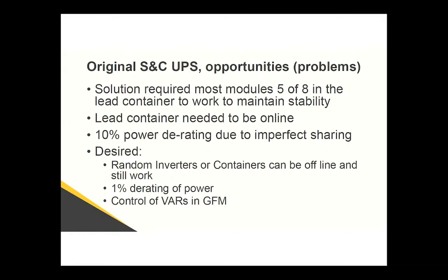And we found that somewhere around 5 inverters was necessary in a multi-container system to maintain the stability. We also had to do derating because the power sharing wasn't that good. So as we went from a single container to multiple containers, we were sharing through both the output inductance and the inductance of the output transformers. And these are all applied at medium voltage. And so we wanted a system that would let us take any container or inverter offline and have a minimal derating in power and allow us to better control VARs.